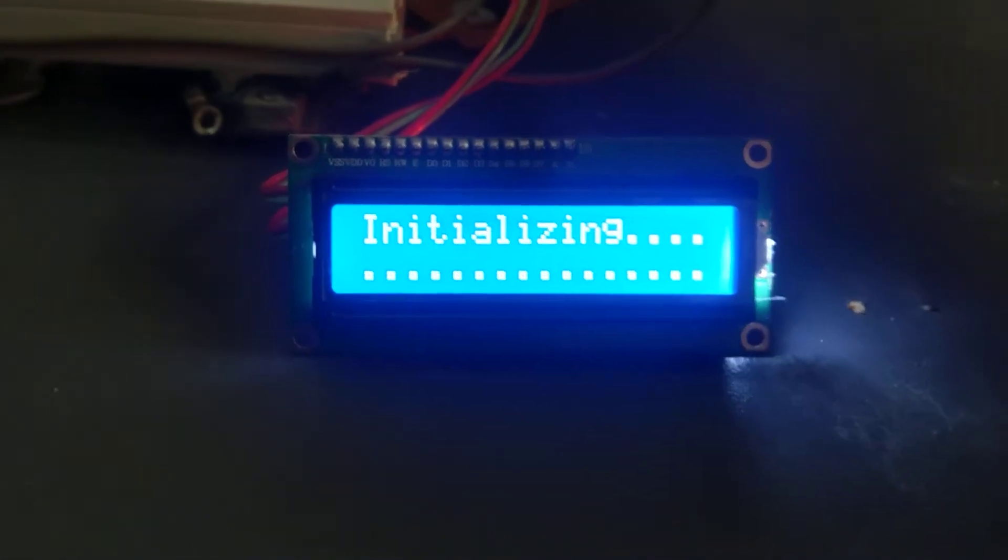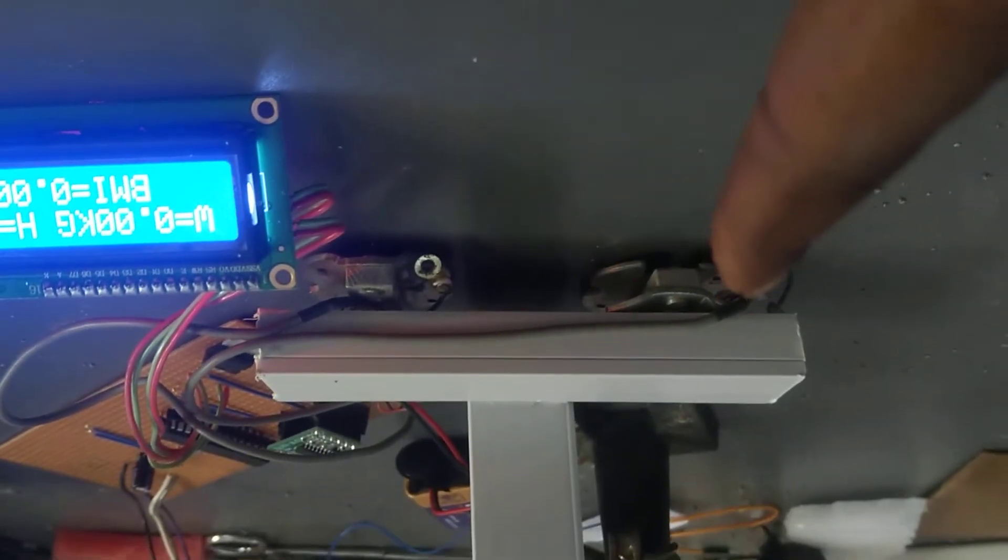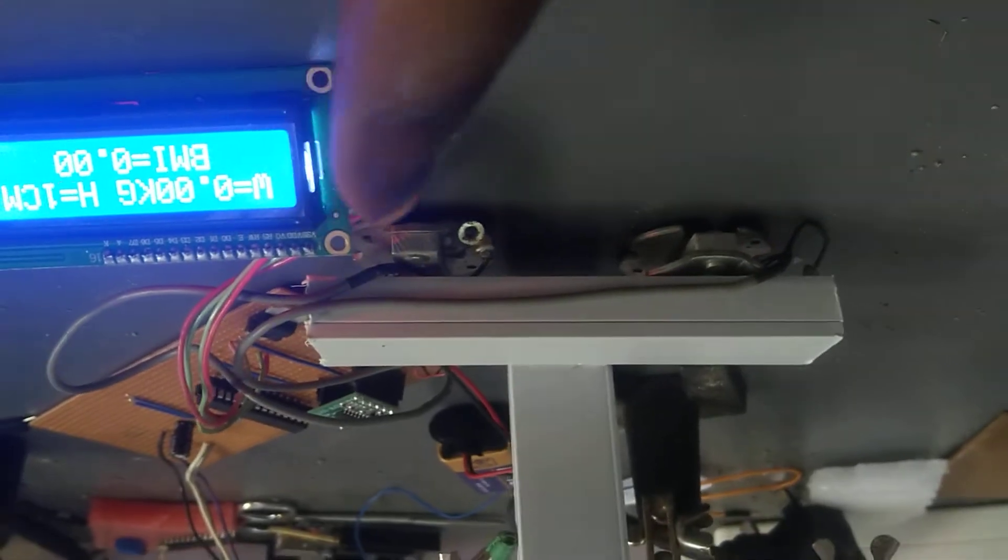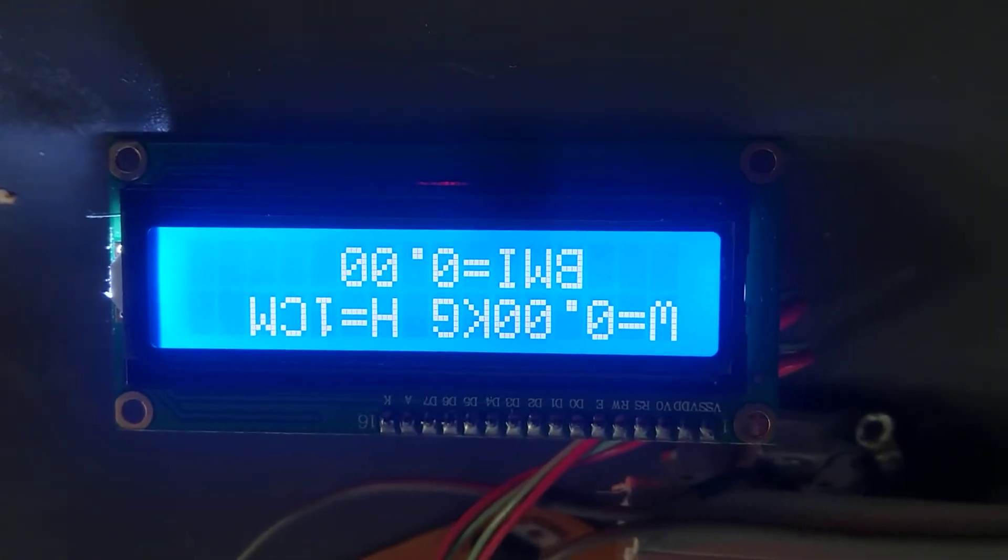Hello guys, welcome to my YouTube channel. Today I'm going to show you a BMI weighing scale. This is a digital BMI weighing scale. As you can see, it has load cells here—these are the two load cells—and we have an ultrasonic sensor here to measure the height. A BMI weighing scale takes two measurements: weight and height.